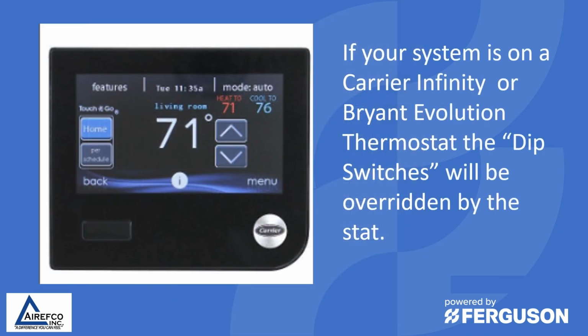Keep in mind that if your system is on a Carrier Infinity or Bryant Evolution thermostat, the dip switches will be overridden by the thermostat. So any airflow changes that you need to make, you will need to make on the stat and not the dip switches.